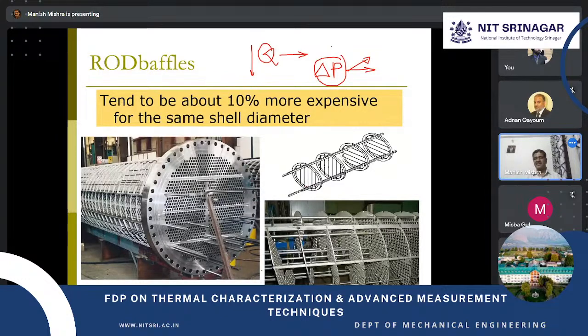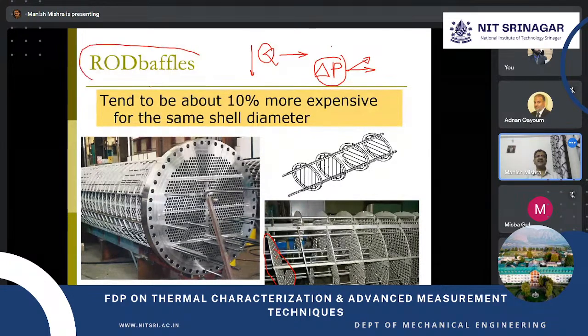Now you can see these are the baffles, and there are perforations. Instead of solid baffles, there are perforations through which the fluid can penetrate partially, but at the same time it will be moving in the vertical, crosswise direction also. This is another variety called the rod baffle kind of heat exchanger, which is basically an improved version of the shell and tube varieties.